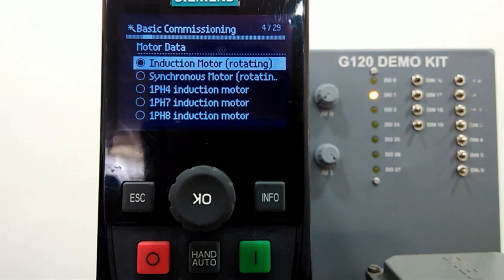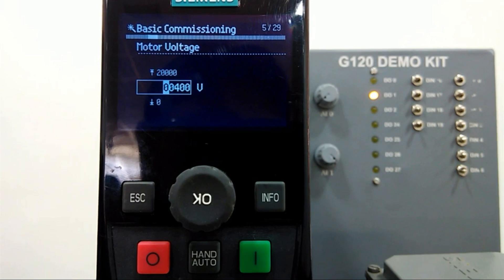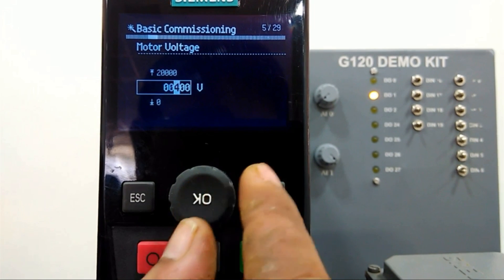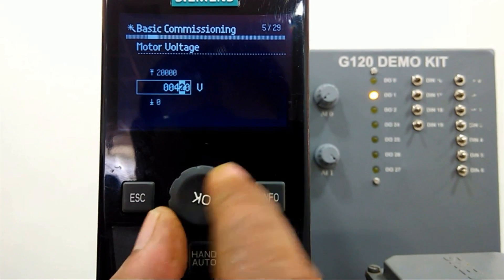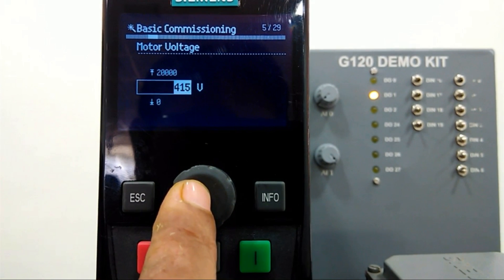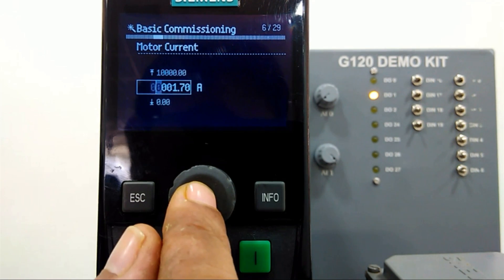Here we will enter motor data. We have connected an induction motor, so we will select that. For motor voltage, as per the motor rated voltage we will enter 415 V. By changing this field we can set the data. For motor current we have 1.70 A, so I will set 1.70.